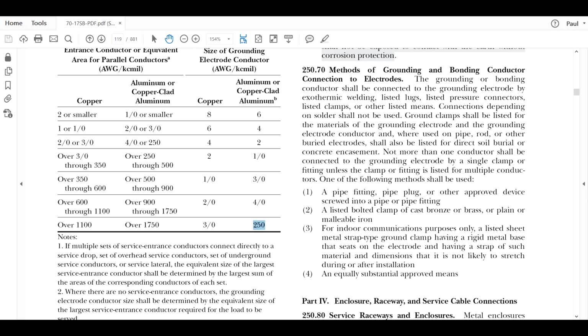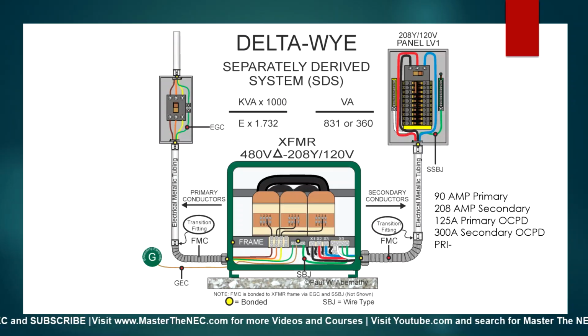Okay. All right, so let's go back to the graphic. So what we've done at this point is we've sized the EGC. We sized the supply side bonding jumper. So over here it was 6. Over here it was a 2. The system bonding jumper was a 2. The grounding electrode conductor, in our case, let's say it's ground rods, so it would only be a 6. And so we've done it.